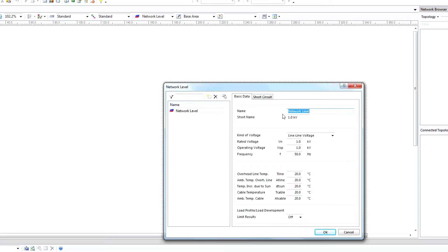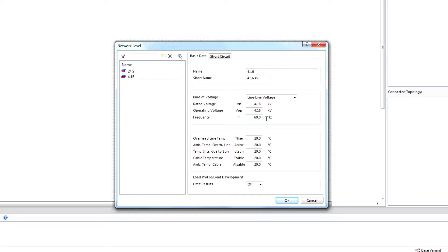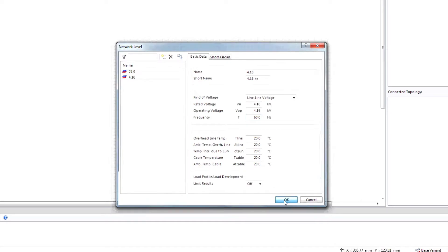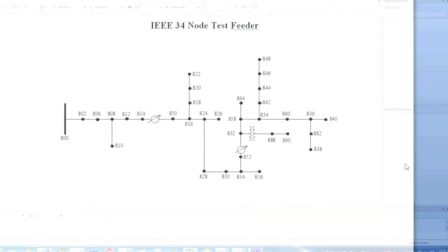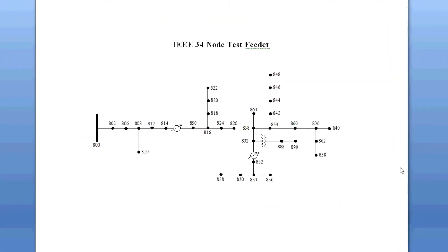Now create a network level that will identify the study voltage level or levels. Click on Network Level, Basic Data. Enter 24.9 kV as the voltage level and 60 Hz for the frequency. You can also enter another voltage level by clicking here and providing the proper information. Here you also have the opportunity to switch overhead line temperature from Celsius to Fahrenheit. Click OK when Voltage Level Setup is complete.